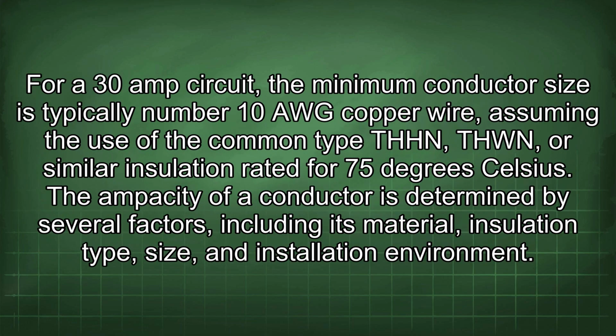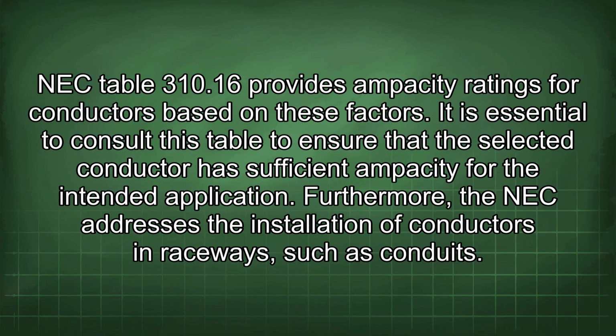For a 30 amp circuit, the minimum conductor size is typically number 10 AWG copper wire, assuming the use of the common type THHN, THWN, or similar insulation rated for 75 degrees Celsius. The ampacity of a conductor is determined by several factors, including its material, insulation type, size, and installation environment. NEC Table 310.16 provides ampacity ratings for conductors based on these factors. It is essential to consult this table to ensure that the selected conductor has sufficient ampacity for the intended application.